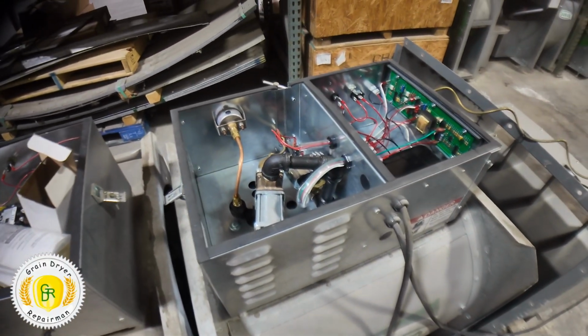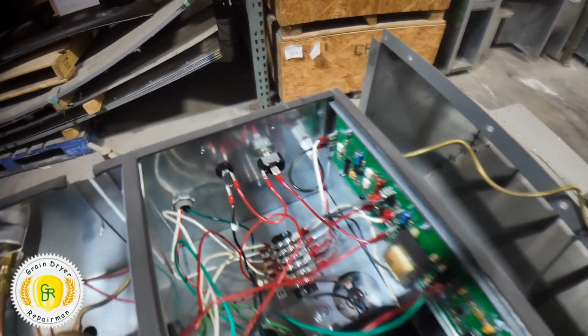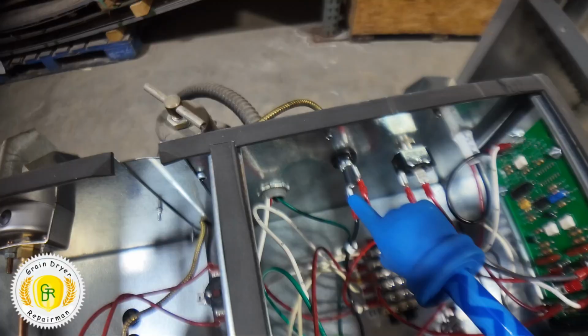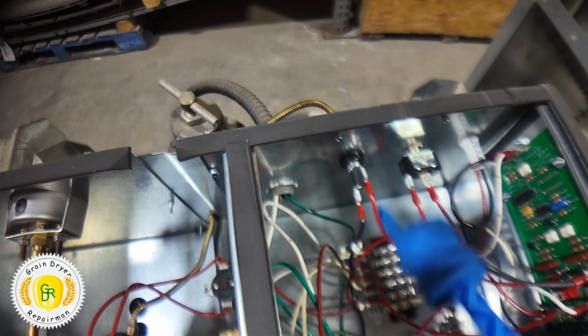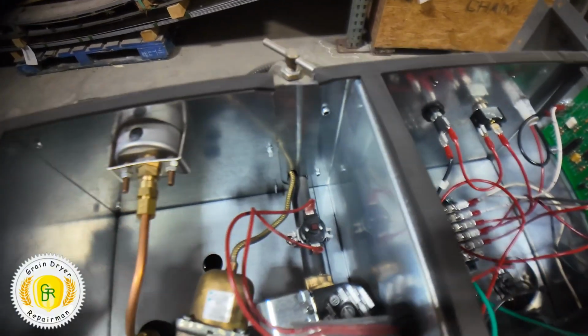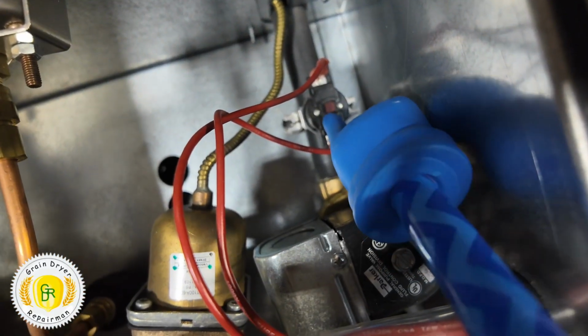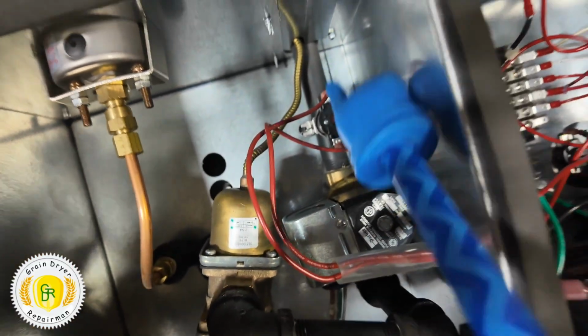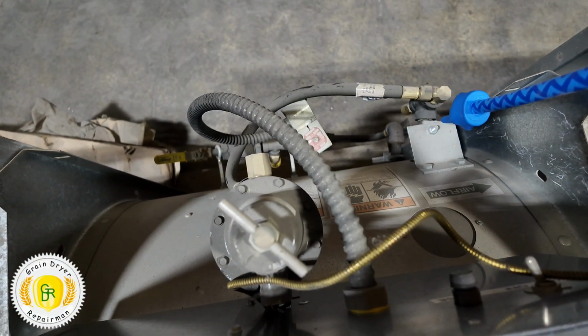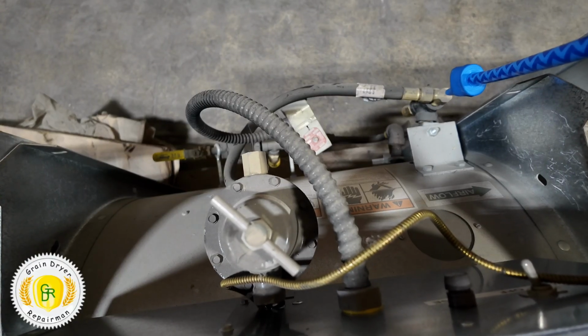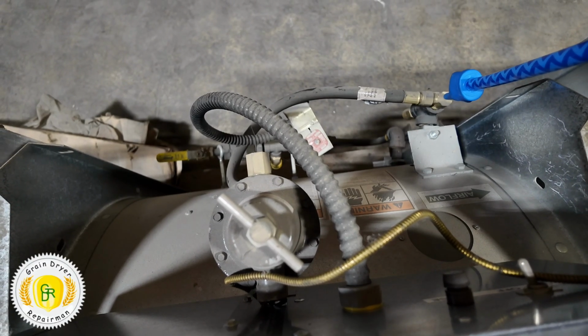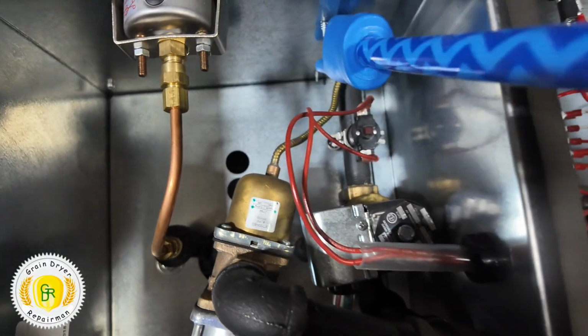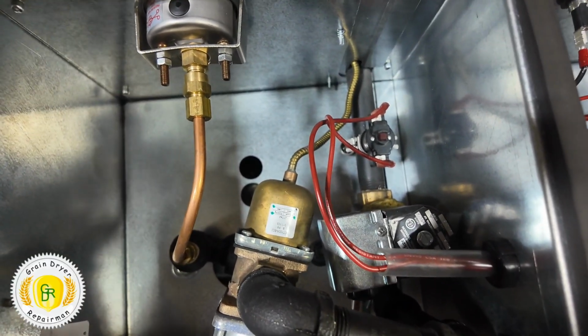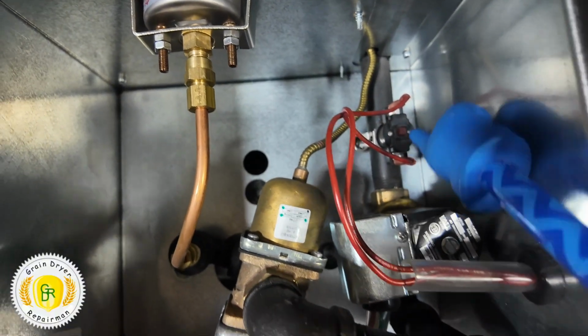If you go to start your burner and it does not start, and you get a voltage tester and verify that you have electric coming to your fuse and going away from your fuse, and it still does not try to burn: if it's a liquid propane, you may have a temperature sensor on your gas pipe where it comes into the box. If the coil is not adjusted right in the flame and it gets too hot, this elbow should not exceed 110 degrees. 90 degrees is perfect. If you have frost on this pipe, it's too cold and you need to adjust the vapor coil into the flame more. If this is too hot, it will trip this. Then you have to reset it.